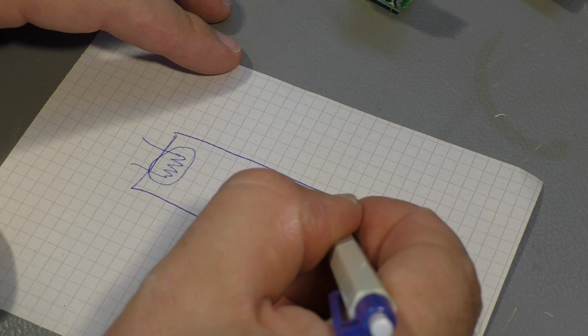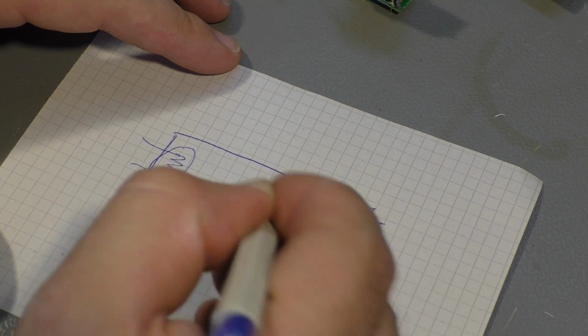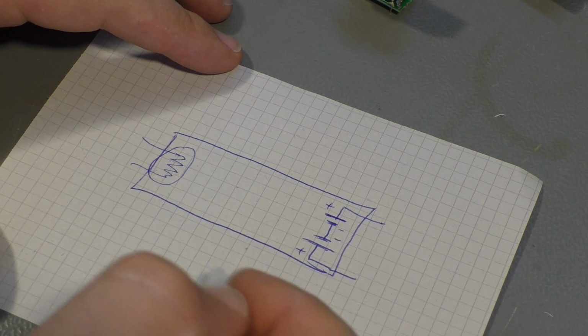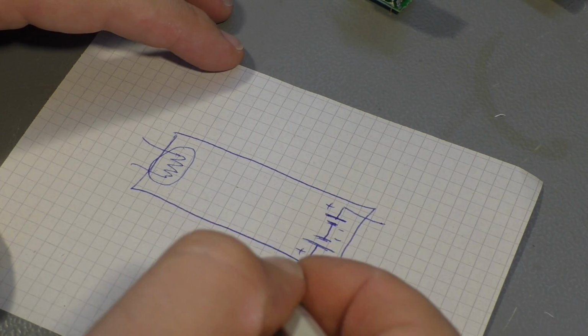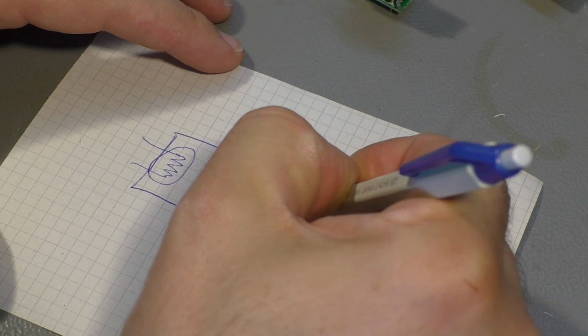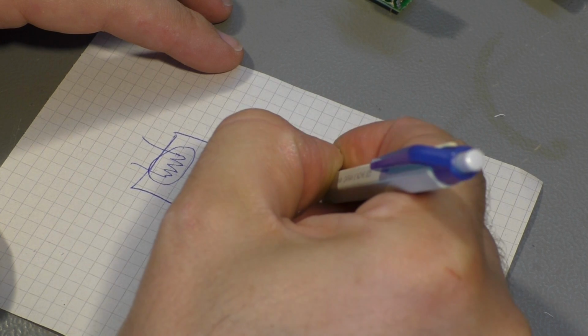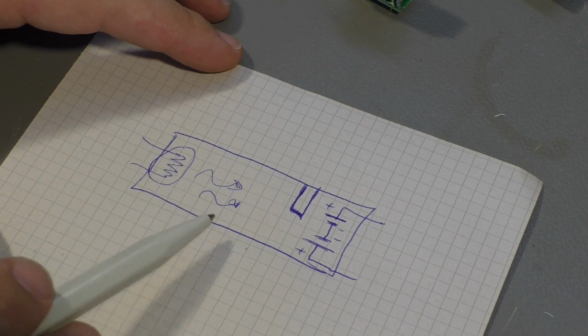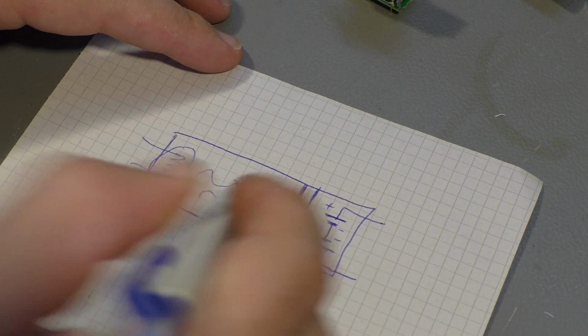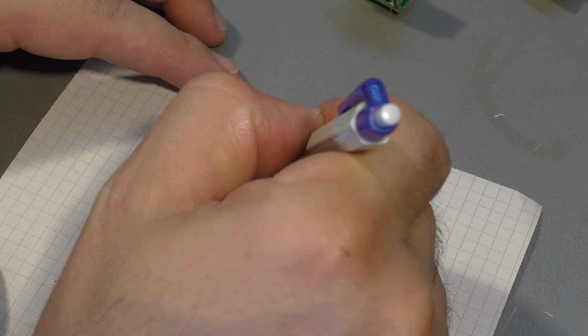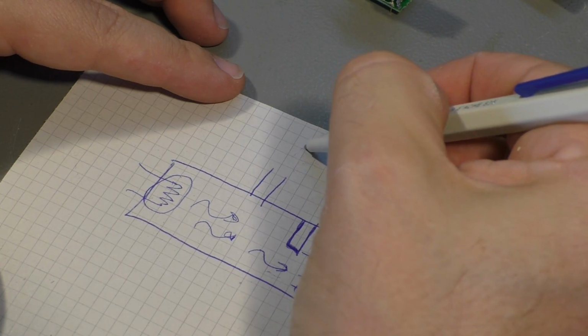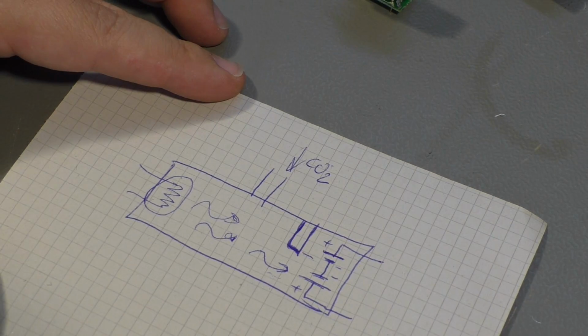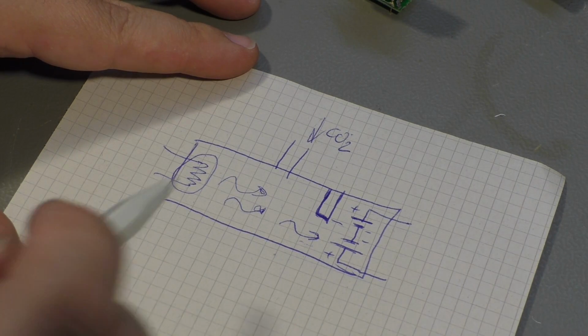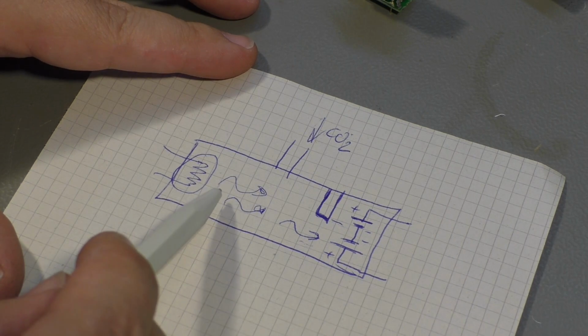So what are they doing? They generate electricity, only a little bit, when they are heated up or when they feel a differential in heat. And one of them is blocked by something that blocks out any infrared radiation that comes from here. So one is blocked, and the other one gets infrared radiation. Now here on the side is the CO2 input, and CO2 has the property to absorb some wavelengths of infrared light.